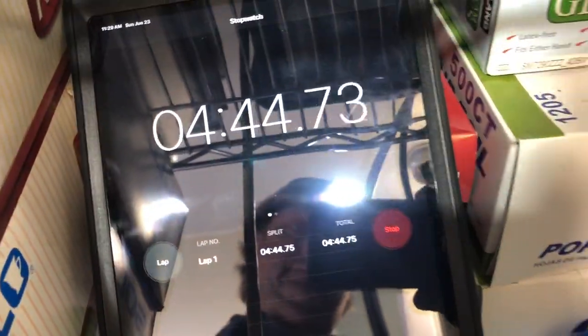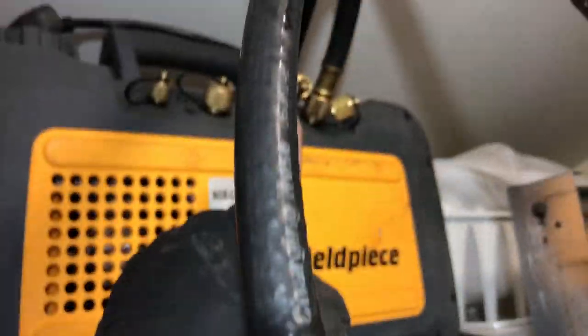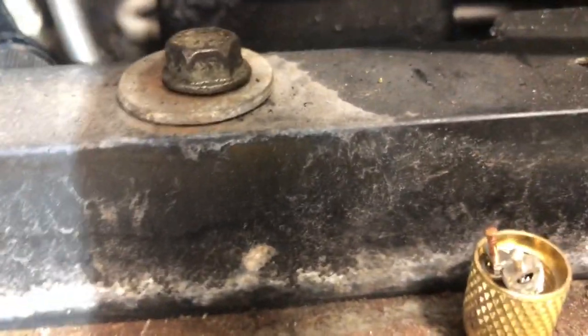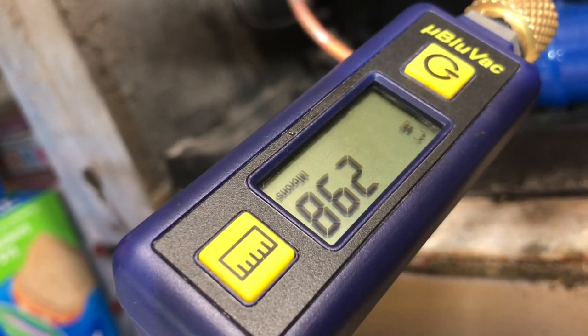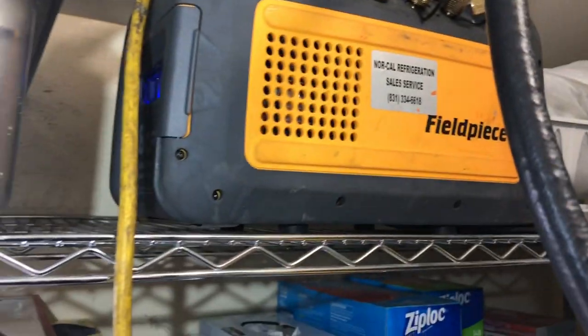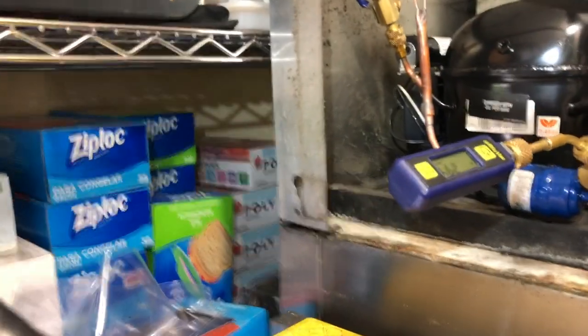We'll tune back in and see how we do. That's with the two Yellow Jacket heavy-duty vacuum hoses — quarter inch connectors to hook up to your system. With the valve core tool removers, the Schrader cores are out. Only five minutes and I'm at 299 microns — so that's the Fieldpiece 8 CFM vacuum pump, the VP85, kicking some mega butts right there.